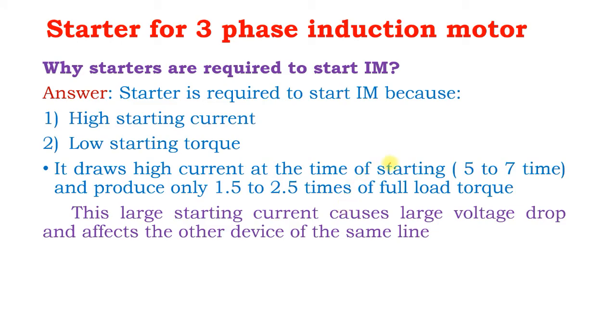Due to this high starting current, a large voltage drop is created in the lines. Due to this large voltage drop in the lines, other devices connected to the same line may be affected. Therefore starters are required. And one more point is, to start the motor in safe conditions, starters are required.